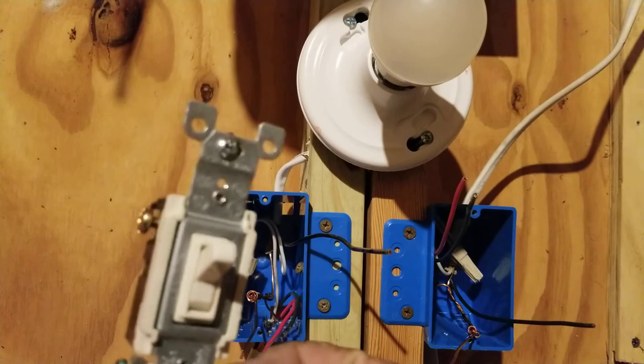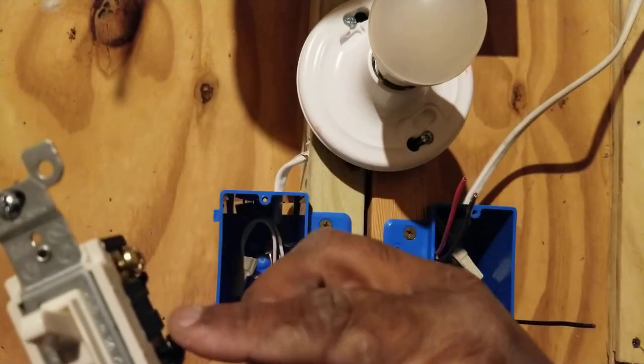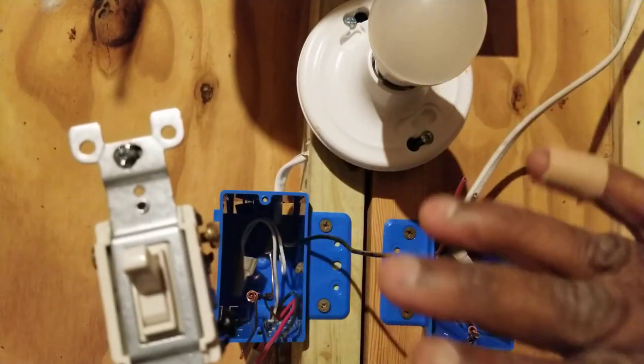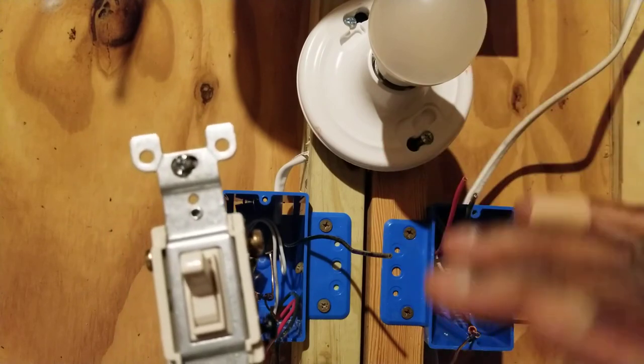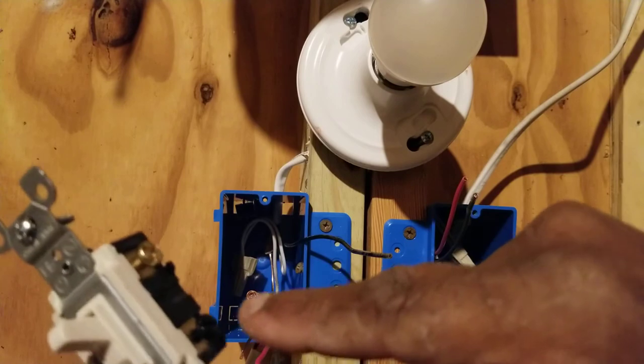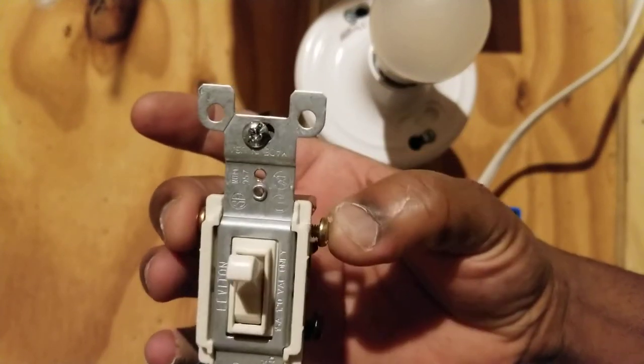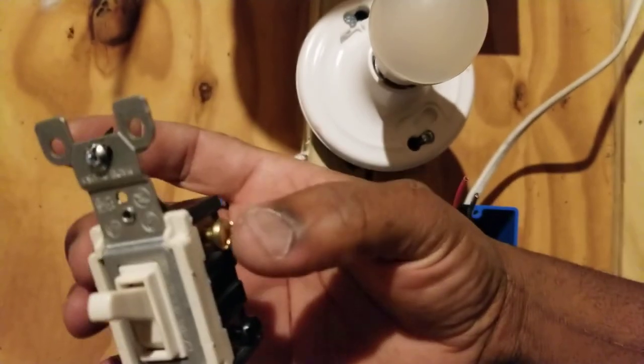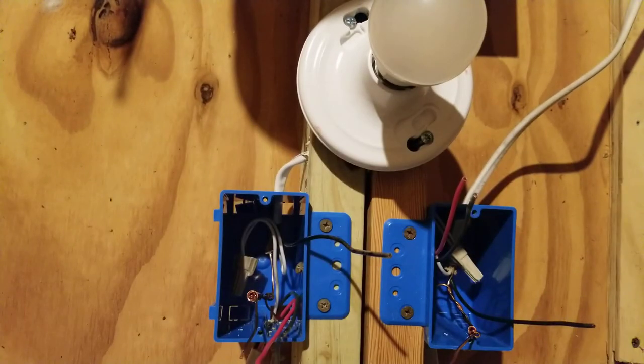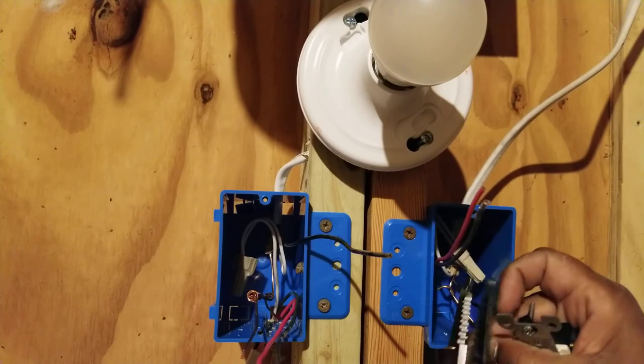It's very important that the travelers go on the traveler screws and the common goes on the common screw. If they get crossed, the three-way switch won't work properly. Make sure the common lands on the black screw and the travelers land on the two copper screws. It doesn't matter which traveler lands where as long as both travelers land on the correct screws.